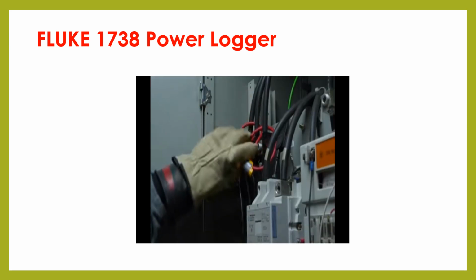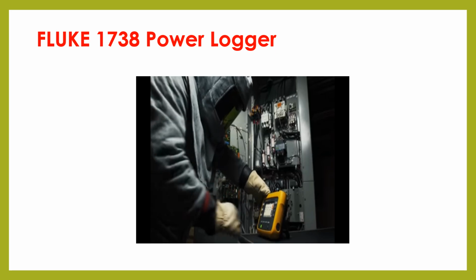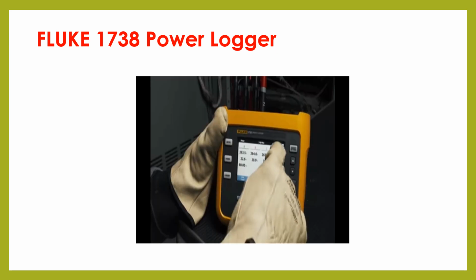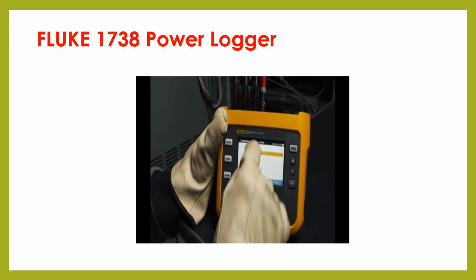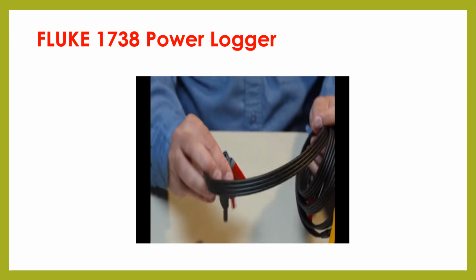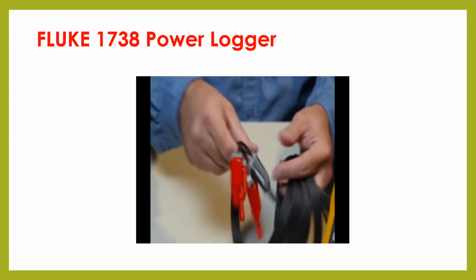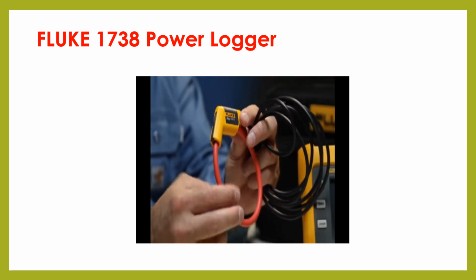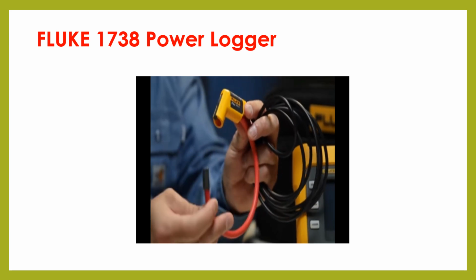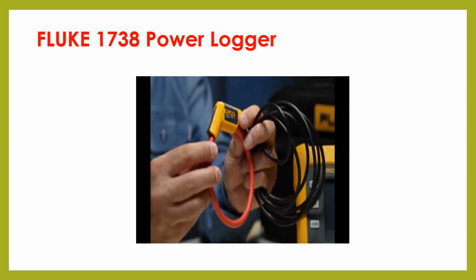Where you install the 1730 will depend on what savings you're looking for. A good place to start is at the building's main service entrance. When installing, ensure the voltage leads go to the correct phases and that the iFlex current probes match the selection compared to the voltage channels.